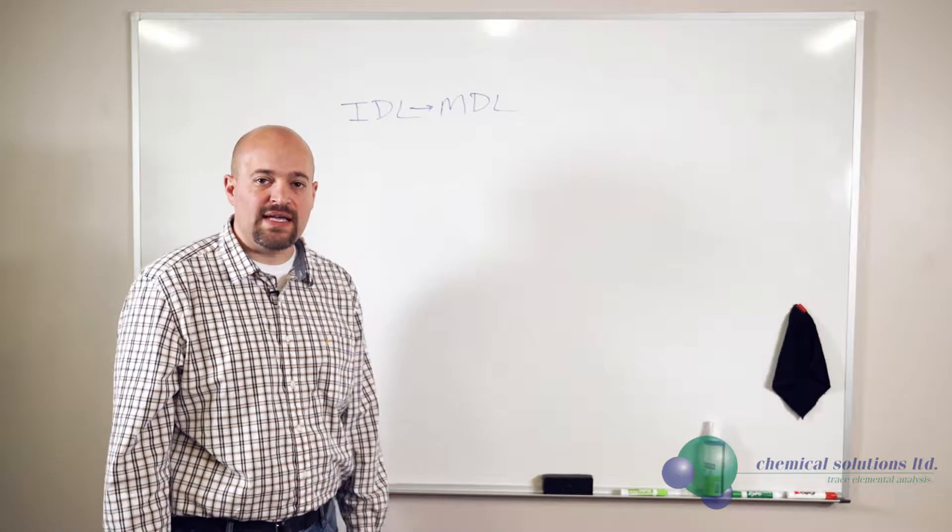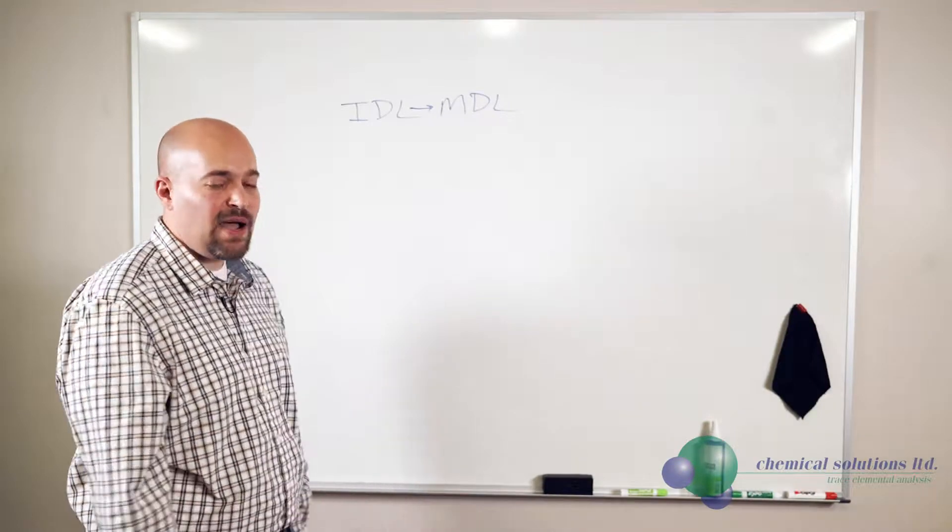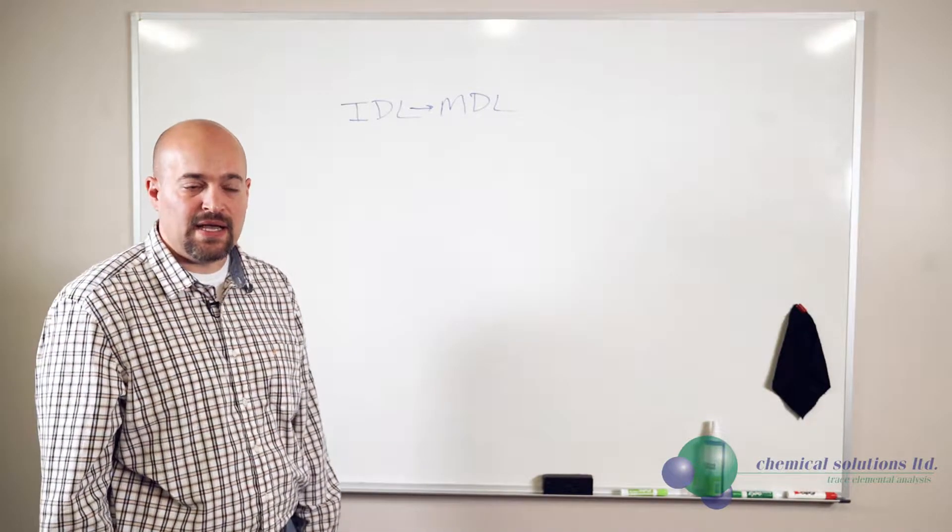One way that we calculate MDLs here at Chemical Solutions is by the equation of three times the standard deviation of seven readings of the lowest calibration standard. That's a common way for us to calculate an MDL.